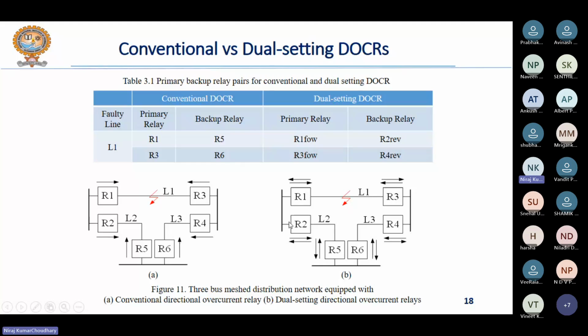R2. Why? R2 in the reverse direction. Earlier, I told you when I was showing the characteristics that each relay will have a pair of settings, one for the forward direction of fault current, another for the reverse direction of fault current, right?